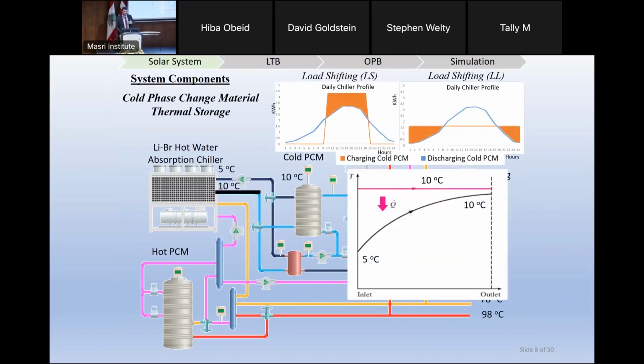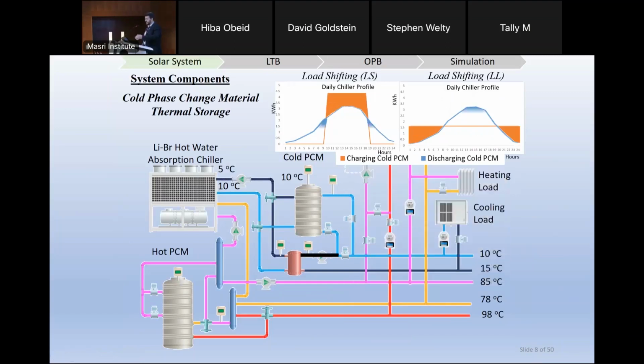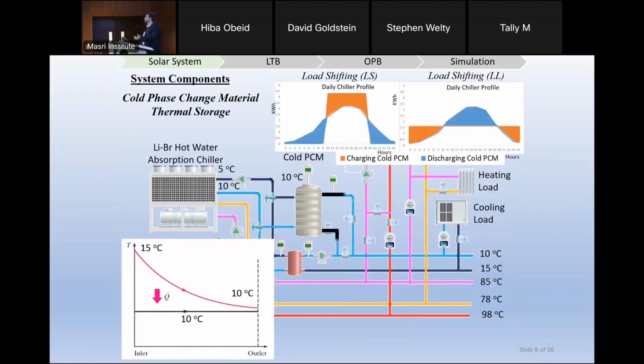So if the energy produced by the absorption chiller during the peak power is greater than that needed, this excess chilled water energy will be stored inside the cold phase change material. Else, it will be discharged and we will get our energy need from the cold PCM.